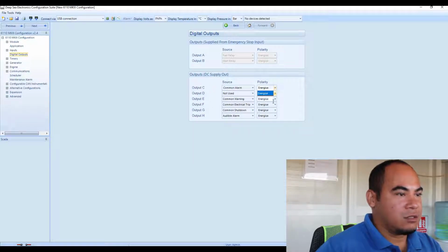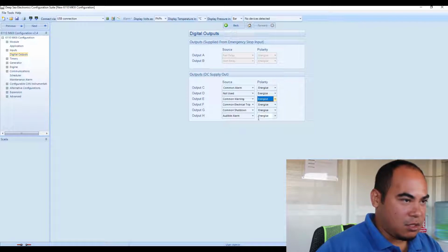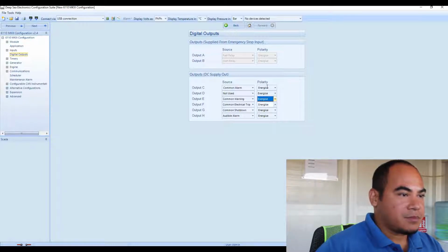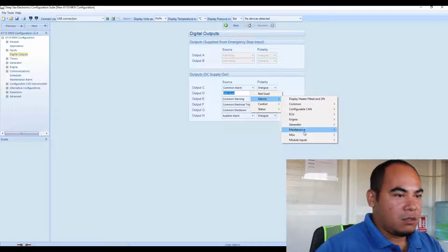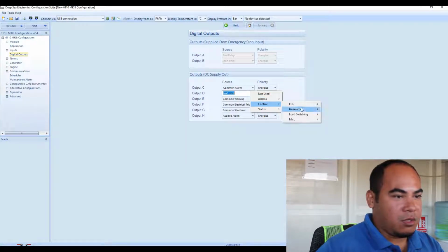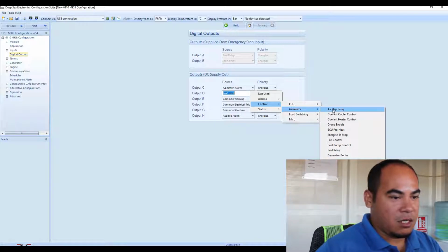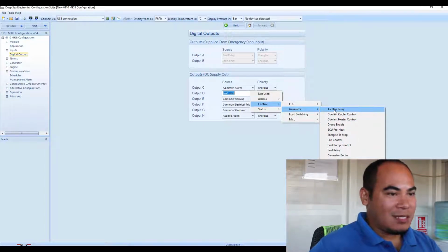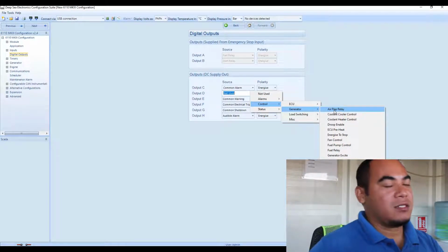If you have other options, you can energize or de-energize the functions. For example, your relay is energized to open or energized to close. So this is the polarity or the switching point of your relay. You have a lot of options here, but always remember it is a positive supply, so you only need a negative or an extra relay to activate that one.